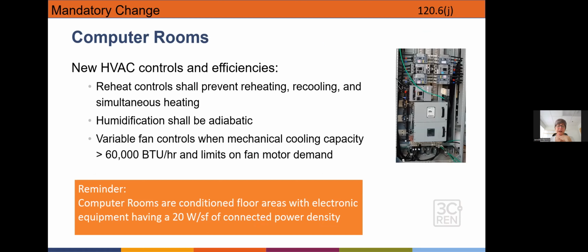For computer rooms, which we see a lot, even in our Tri-County region - this specifically is for computer rooms that have 20 watts per square foot of connected power density load. These computer rooms now have new HVAC controls and efficiency requirements, including that reheat coils shall prevent reheating and recooling and simultaneous heating. There's some new requirements on how the humidification shall be designed and what kind of equipment can be used. And there's also more language about variable fan controls when mechanical cooling capacities of around 60 kBTU per hour are specified.